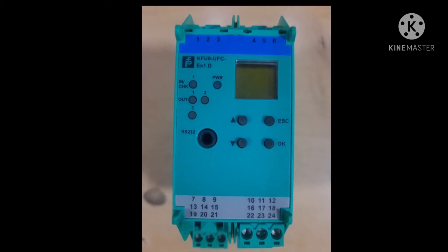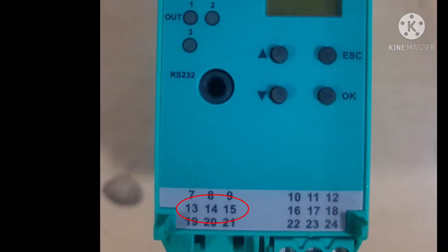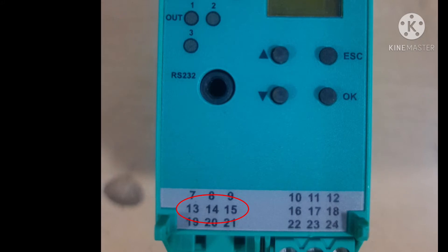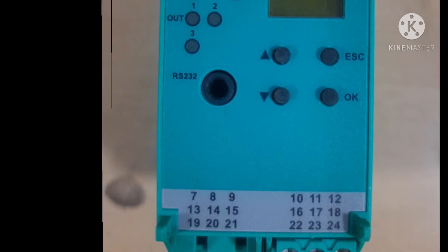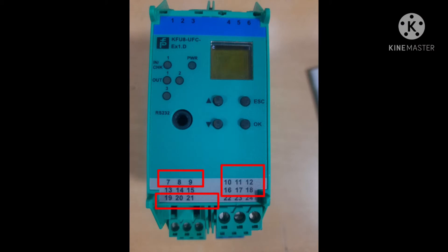Channel number 5 is the second input, which is a non-intrinsically safe channel, so we are not going to connect anything to terminals 13, 14, and 15. The rest of the channels are output channels, which you can see in the image.